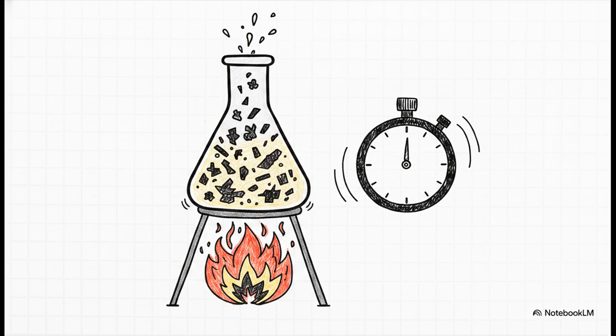By using super strong chemical oxidants, usually potassium dichromate mixed with boiling sulfuric acid, in what's known as the closed reflux method, we can totally obliterate all the organic matter in the sample. This aggressive reaction takes just 2 to 3 hours. When you contrast that agonizing 5-day wait for BOD with a 2-hour turnaround for COD, you can see why COD is the absolute workhorse for real-time monitoring in treatment plants.